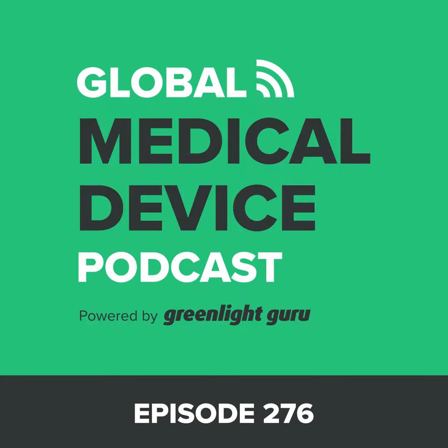In the US, all your approval process in establishing registration and product listing, that was untouched and remained in place. And UDI was simply a new requirement. Not so in Europe. UDI becomes one of the many things that a manufacturer has to learn and be educated on and then respond to. And there was no grandfathering of products. So basically your whole portfolio now has to be reevaluated to the new regulations to see if they meet.